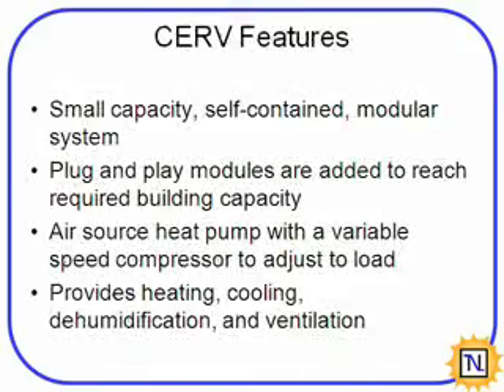So some features of the CERV that make it well suited for conditioning in these super insulated, super sealed homes are that it is a small capacity. With standard systems, it's hard to find very small. It's self-contained and it's a modular system. So based on the size of your house, you may put 2 or 3 of these together to build up to that. That modularity gives you capacity control, as well as it has a variable speed compressor. So within each module, you're able to vary this compressor speed, which gives you additional adjustability to the load. And then within one self-sealed box, you're going to have heating, cooling, dehumidification, and ventilation as well. So it combines all the things you need for this type of house conditioning into one package.